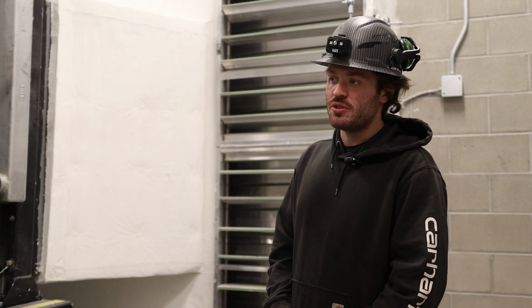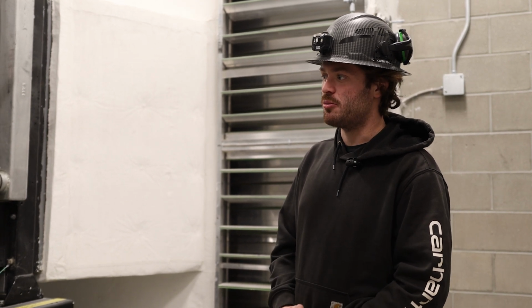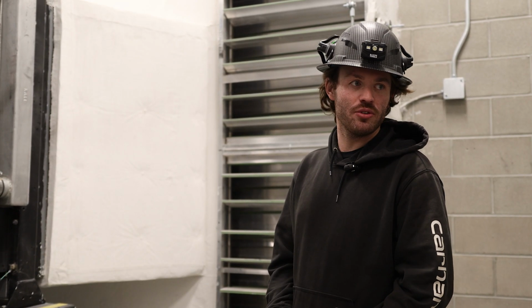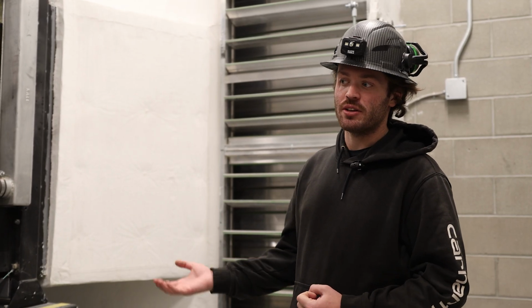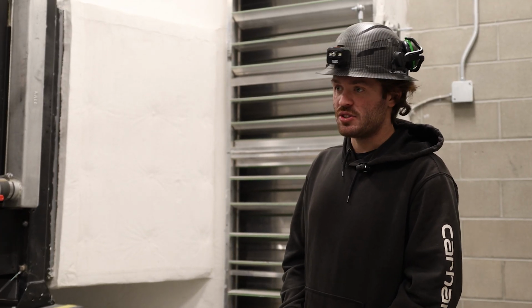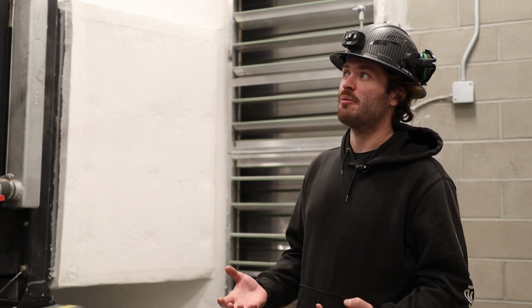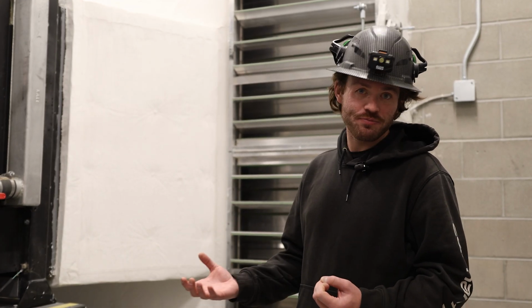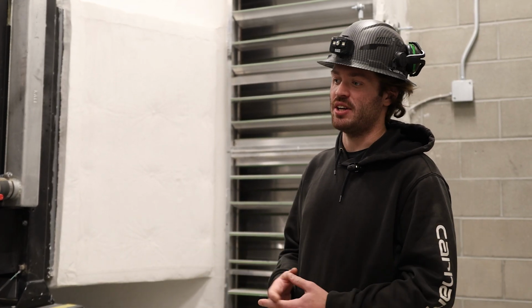You always want to, as much as possible, fill it with winter blend diesel. So even in summer months, if you're fueling it, try to specifically request winter diesel fuel. You don't necessarily know how long the fuel is going to be sitting in this. It could be up to years on end if the unit is not running much or not running much under heavy load. So if it were to get cold in this room, for example, it could cause the fuel to gel. Pretty unlikely, being that it's inside.